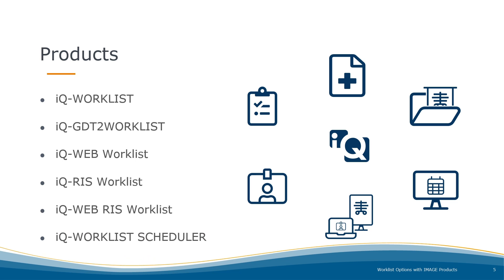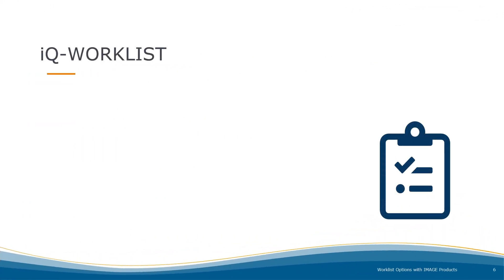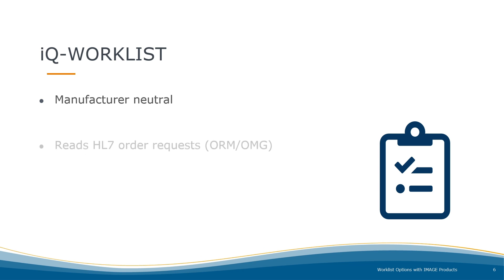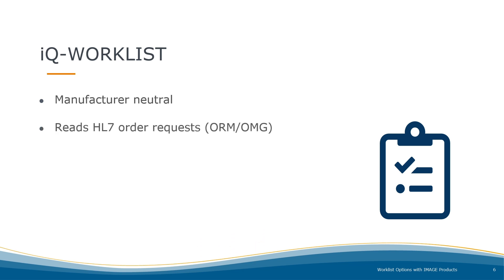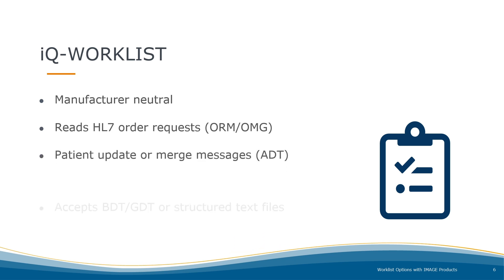Let's talk about IQ Worklist first. IQ Worklist can interface with virtually any radiology, practice, or hospital information system, read scheduling data, and create DICOM worklists for imaging modalities. In addition, it can read HL7 order requests, patient update or merge messages like ADT, and also accept BDT, GDT, or structured text files as a data source.